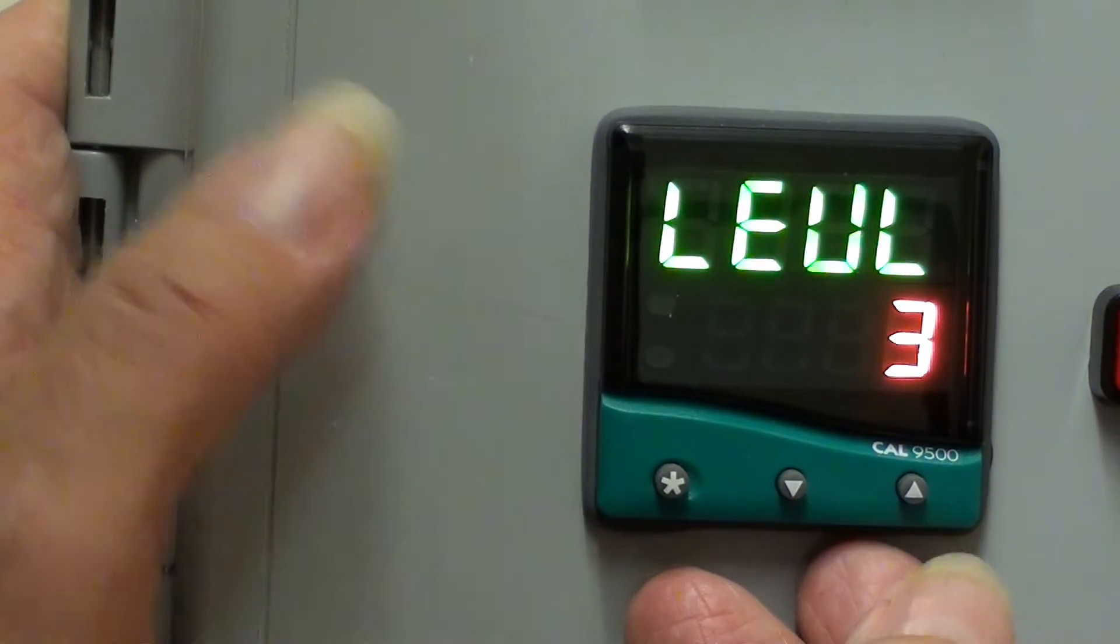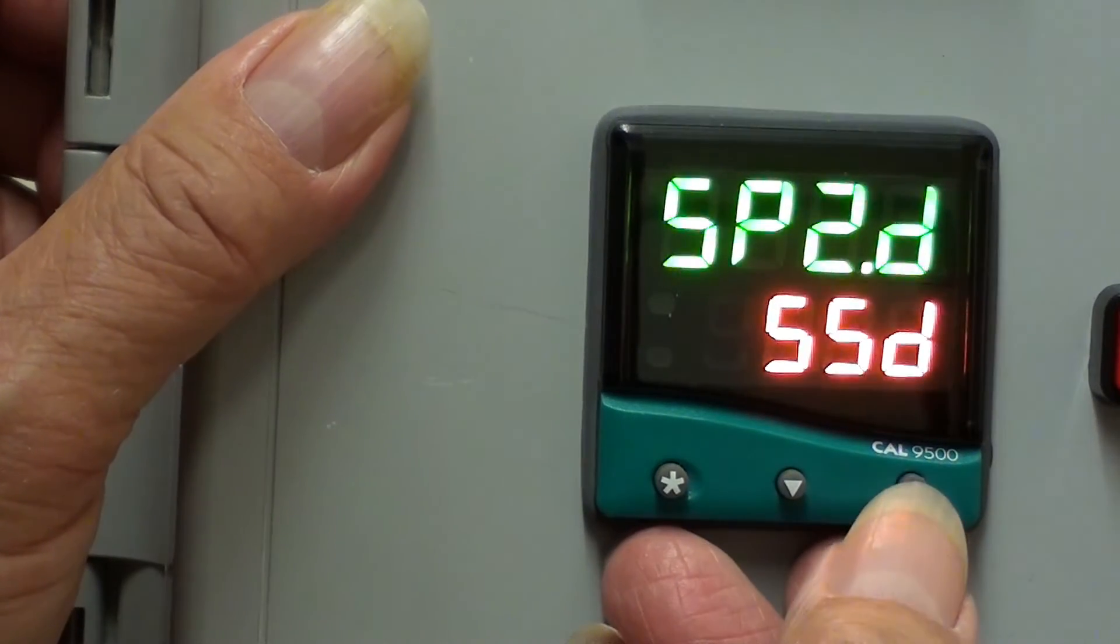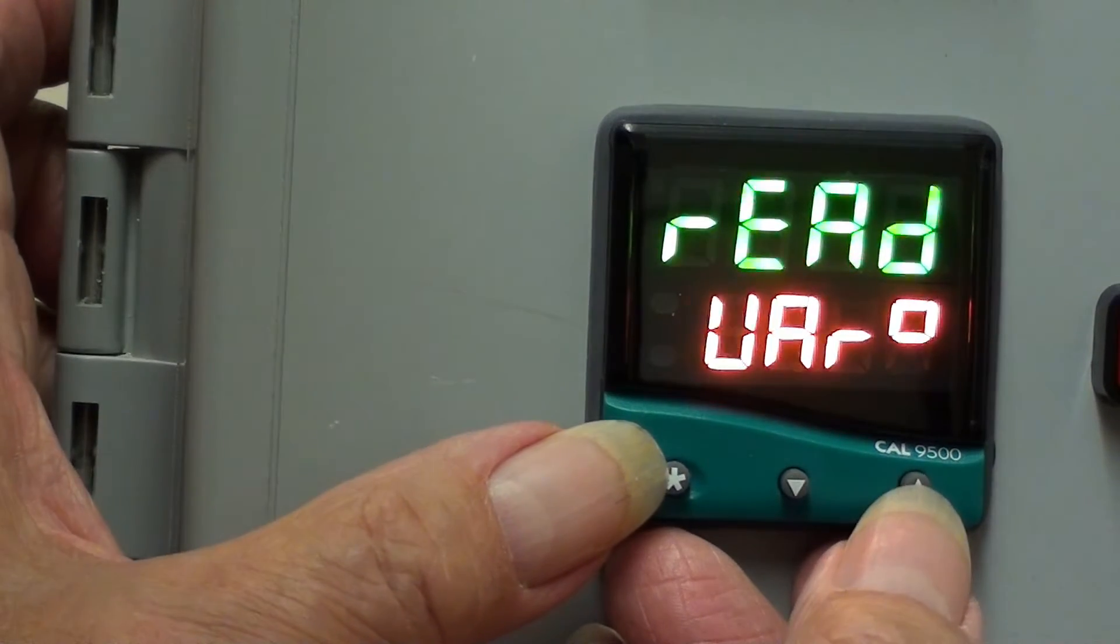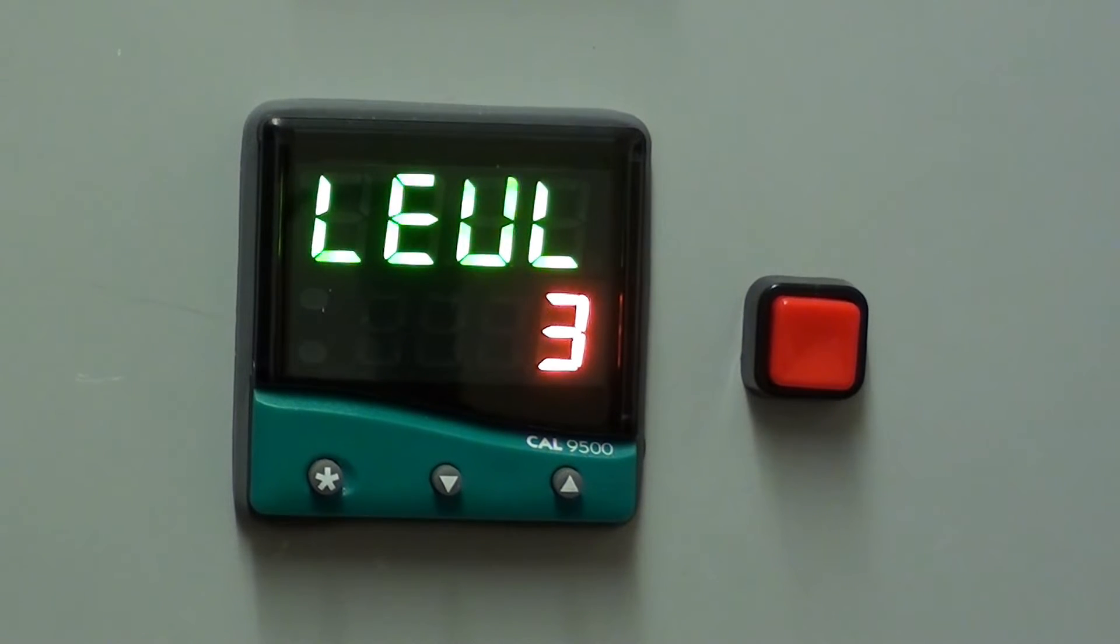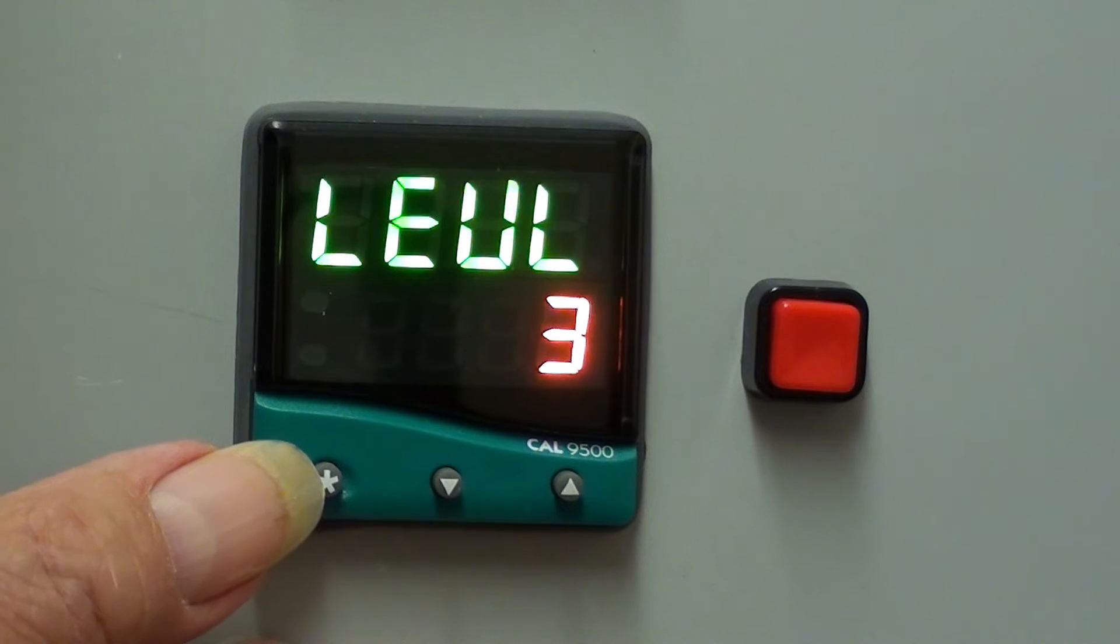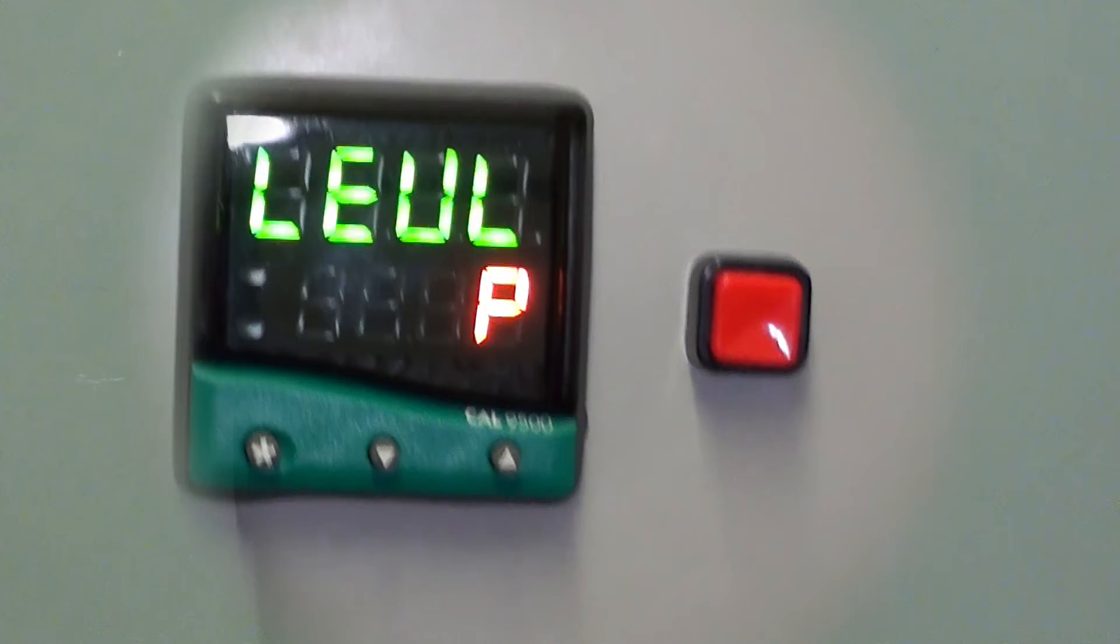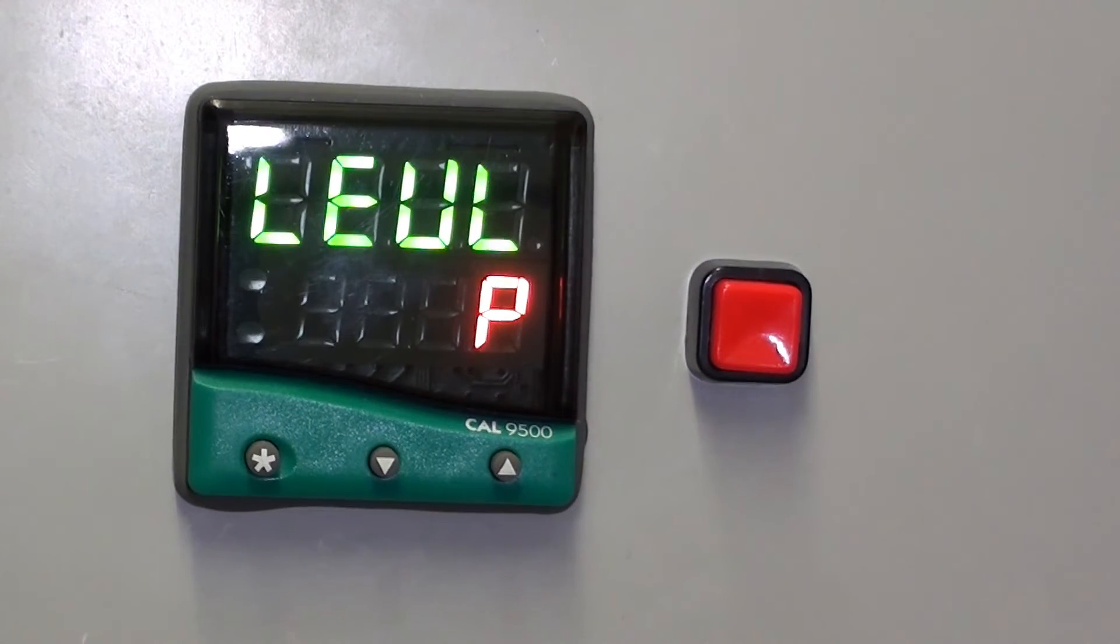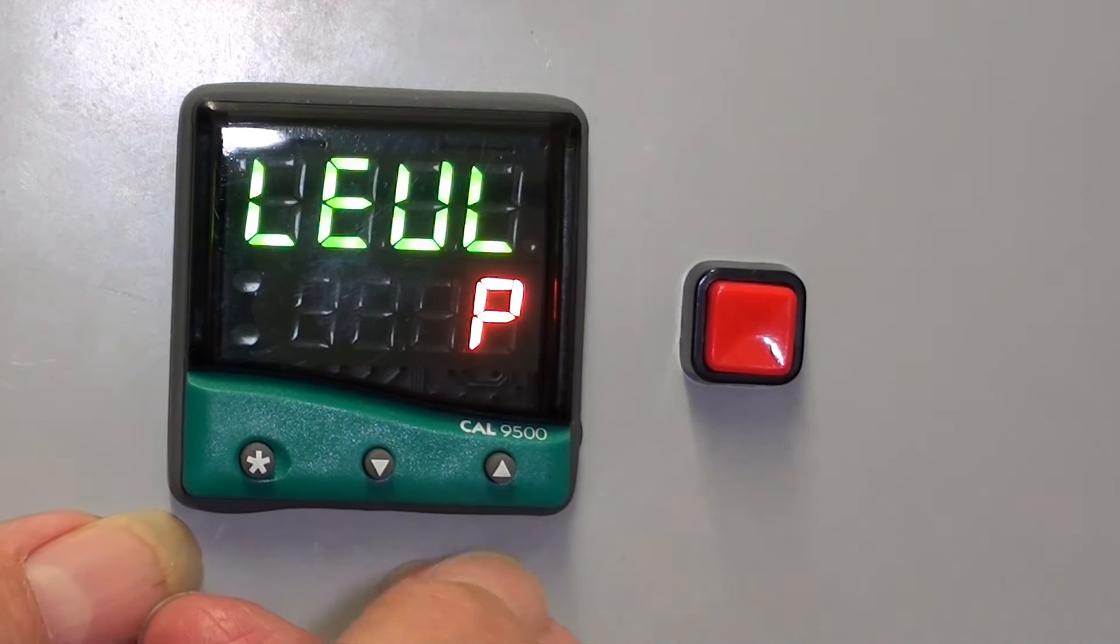Level 3. At level 3, we can select the type of outputs. Relay, SSD and so on. If we want to create a program or a profile, we have to go to level P. So, hold the star, the down arrow, P. In level P, we can create up to 31 programs and a total of up to 126 segments.